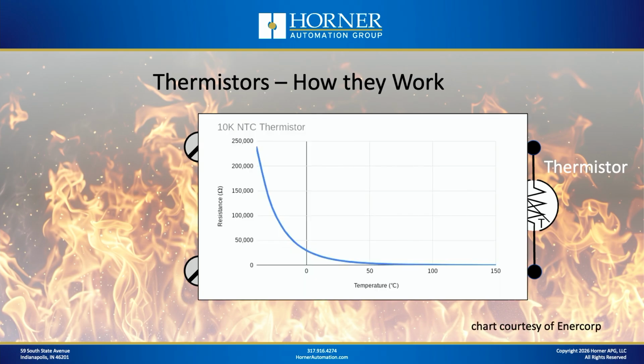And here is a chart showing an NTC thermistor, a 10K NTC thermistor, which is the most common category of thermistors that are used in industry these days. Okay, but you can see even at around 0 degrees C, you're talking 30,000 ohms of resistance there. But a very limited temperature range, obviously. You don't go up nearly as high as RTDs and thermocouples do. The most common thermistors that are in use are 10K type 3 and 10K type 2, all right? So it's very important that you make sure that you buy the right ones to match your measuring instrument.